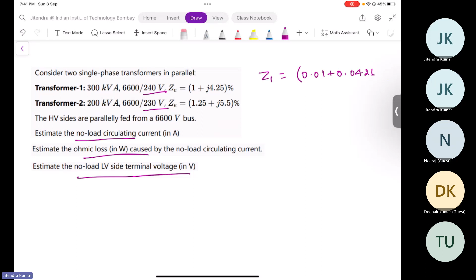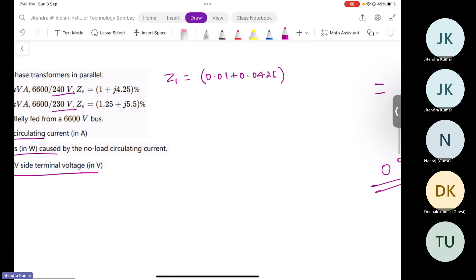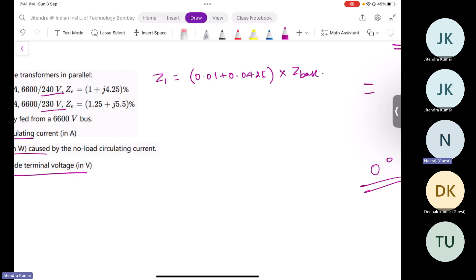It is given in per unit, and to calculate circulating current we need actual values. So the first thing we need to do is compute the actual value. Z1 equals 0.01 plus 0.0425, multiplied with the base value, into Z base.